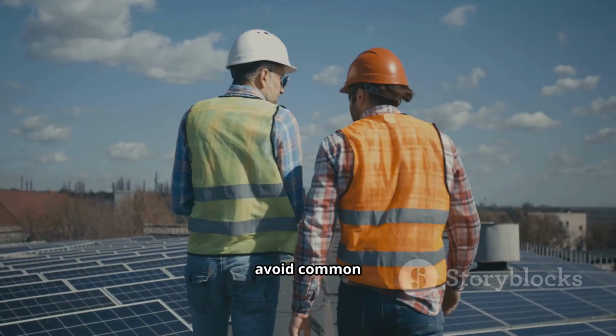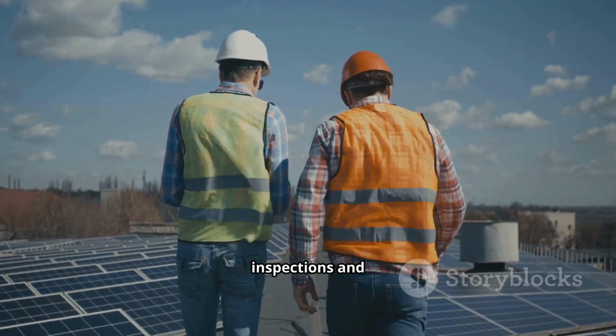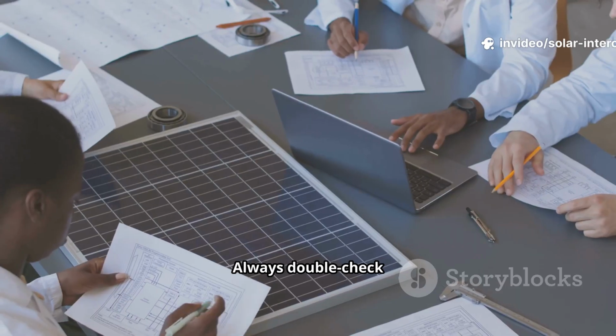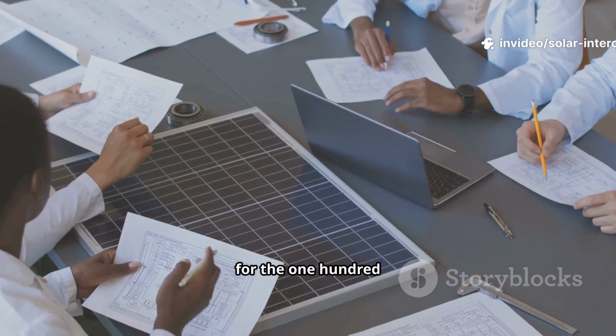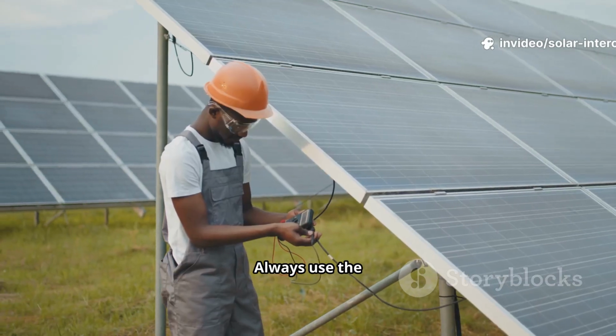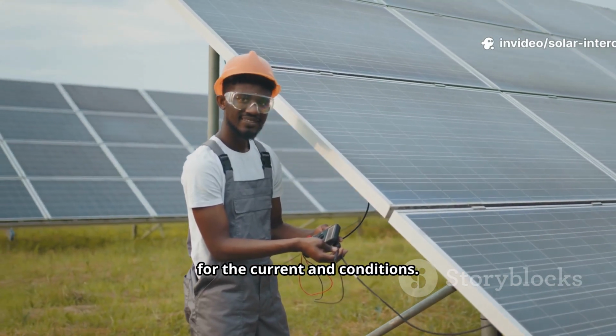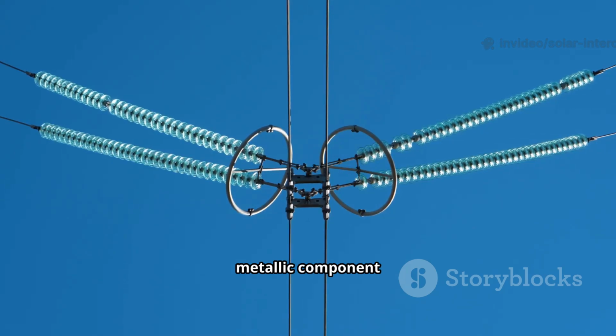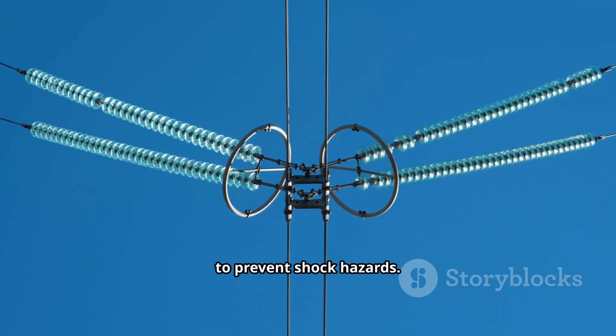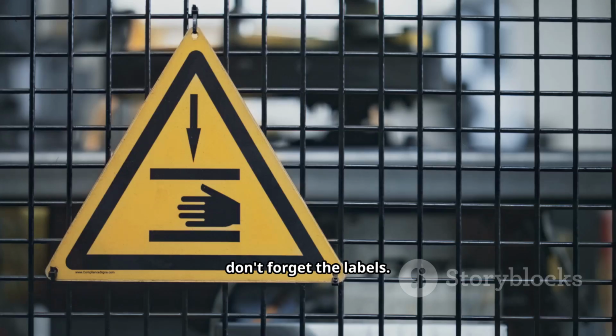Third, avoid common mistakes that lead to failed inspections and unsafe conditions. Always double-check your calculations for the 120% rule. Always use the correct wire size for the current and conditions. Ensure every metallic component is properly grounded to prevent shock hazards, and finally, don't forget the labels.